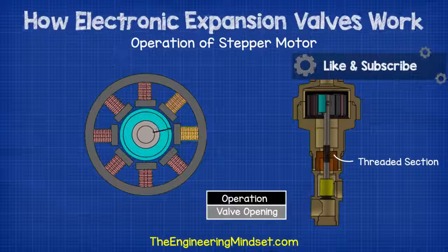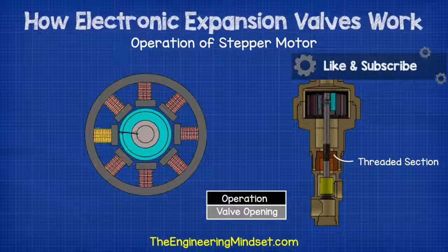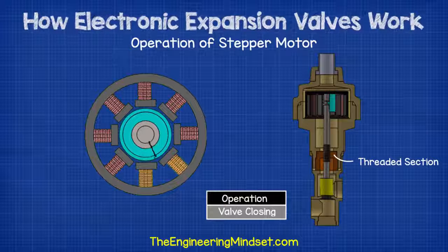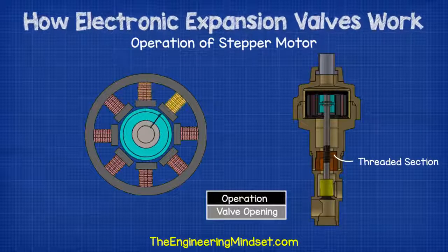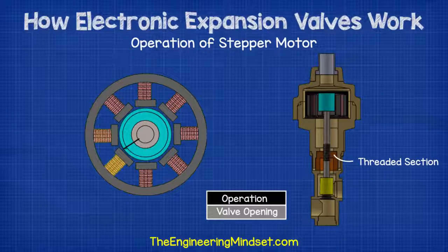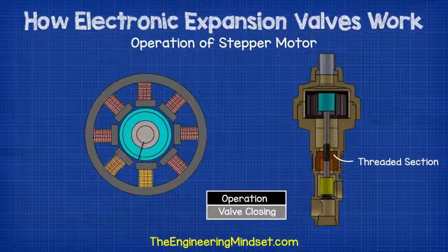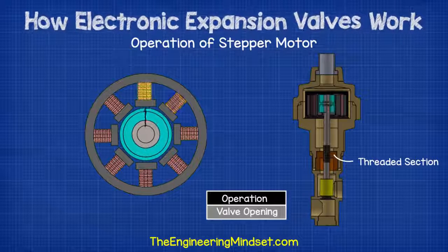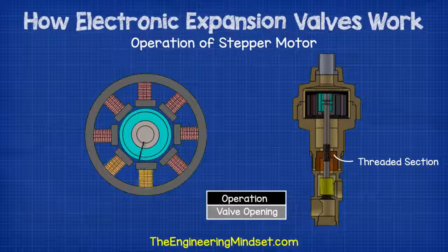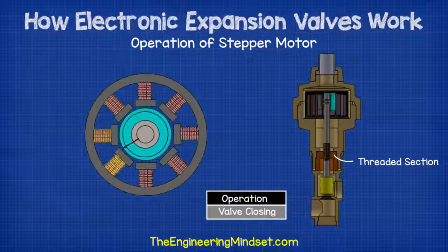As the assembly is pulled down, it will cause the valve needle to reach the seat, reducing the gap between and restricting the flow of refrigerant. When the signal is sent to open the valve, the assembly will rotate in the opposite direction and the threaded section pulls the assembly up. This opens the valve and moves the needle away from the seat, allowing more refrigerant to flow.